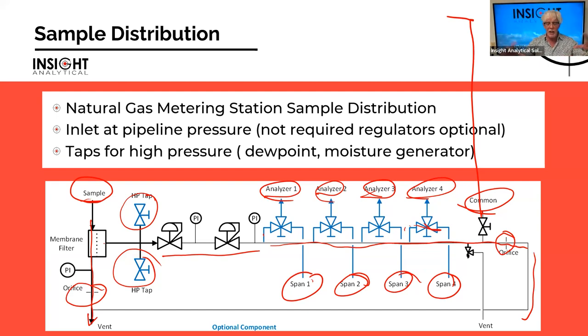Flow orifices control the bypass flow on the sweep side of the filter, and we also keep a continuous flow through this entire path so that if these aren't used and they're blanked off, they don't become dead legs. We've taken that entire sample system which you can imagine would probably take up a pretty decent size back panel, and there it is implemented into one block. You can see there's three valves there. We put blanking plates on if you don't need to have those extra streams.